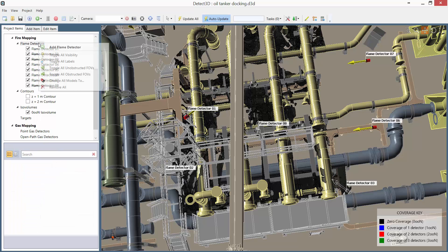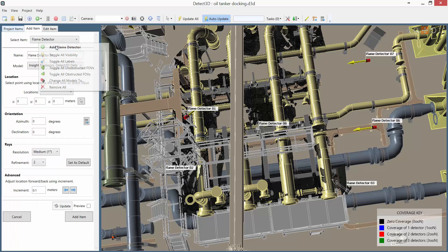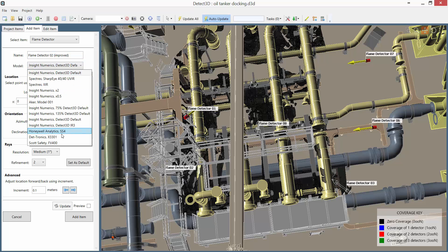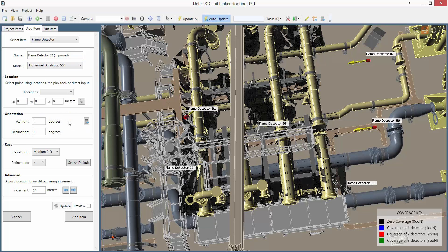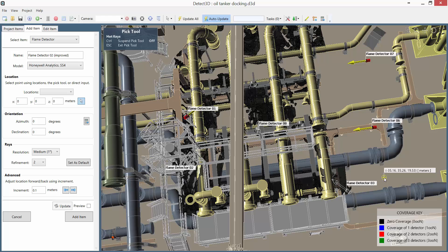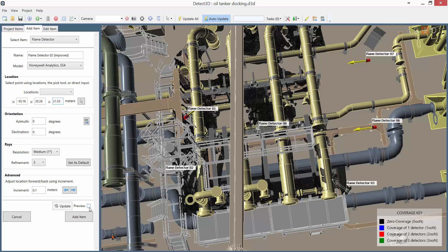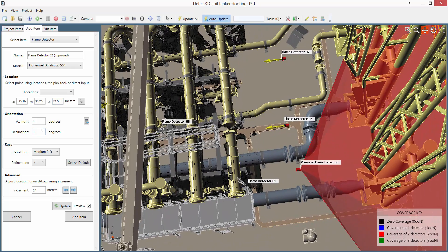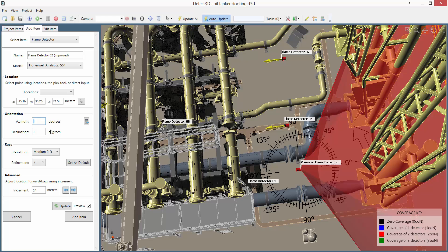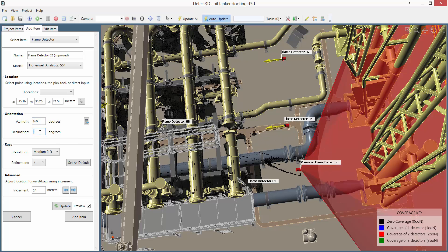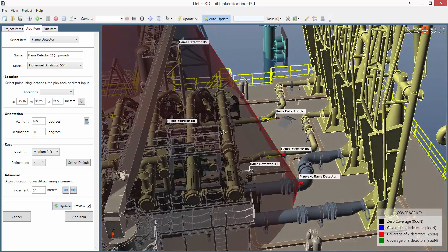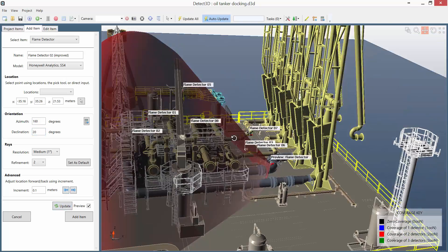Now I'm going to add the new detector as a replacement Detector 02. Right click and select Add Flame Detector. I'm going to call it Flame Detector 02 Improved. I'm going to select the same model as I have for the other detectors in the simulation. I'm going to position the detector fairly close to Detector 6, giving it a couple of meters of elevation. And then adjust the azimuth to 160 and the declination to 20, and update that to give me a preview of the detector location. And that looks pretty good.